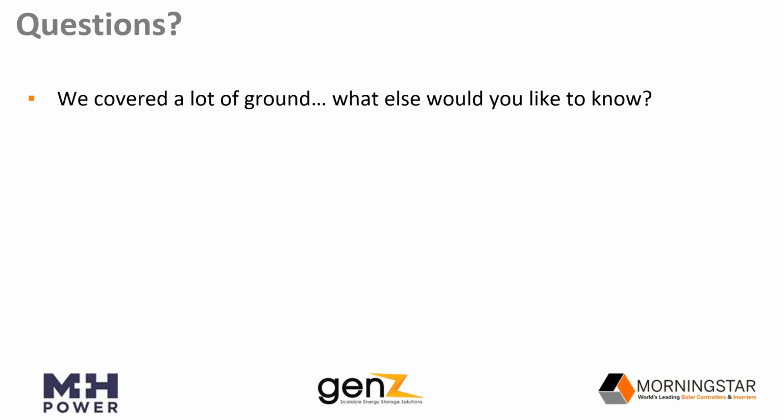Sure. Thanks for the question, Stephen. I take it you meant 100% depth of discharge. If so, if you hop onto our website, it's in the data sheet and product manual, clause 13, appendix D. We recommend 80% depth of discharge, where the cutoff is about 50.38 volts, but we can also quote 100% depth of discharge, and the lowest cutoff point is 40.4 volts. So 40.4 volts is the answer for 100% depth of discharge.